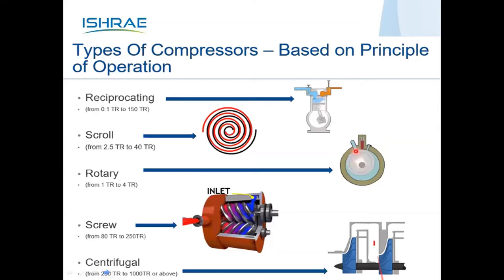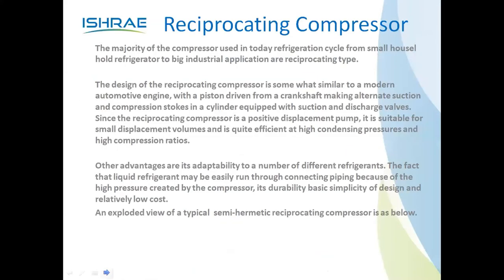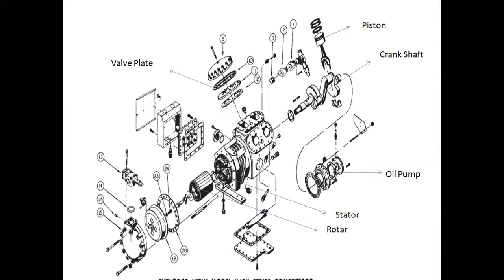Looking at the reciprocating compressor cross-section: a crankshaft connects to a piston via connecting rod, reciprocating within a cylinder liner and compressing gas. This is a semi-hermetic compressor where the motor is not separated — the rotor is on the same shaft with the stator winding on the compressor body. A semi-hermetic reciprocating compressor avoids refrigerant leakages, which is important for protecting our ozone layer.